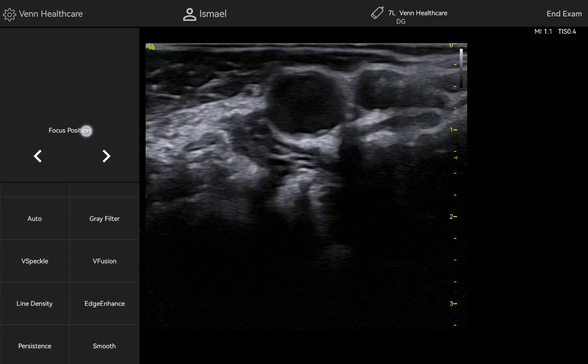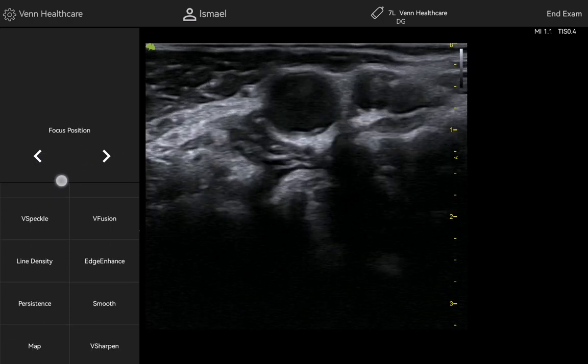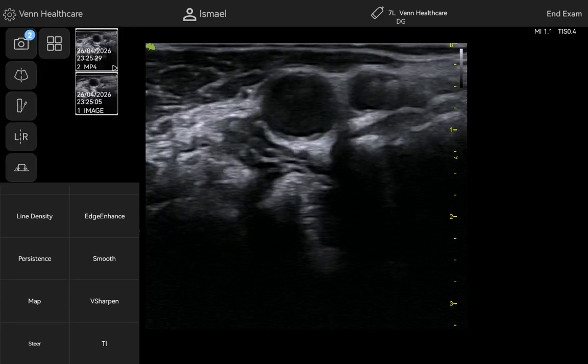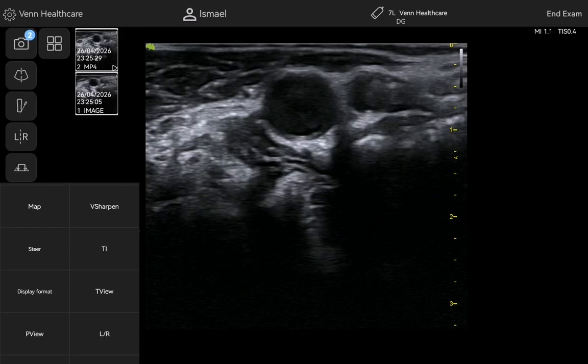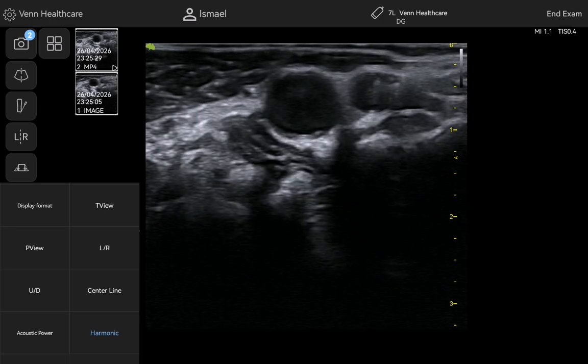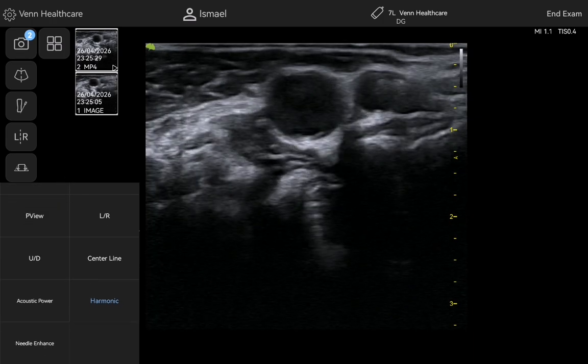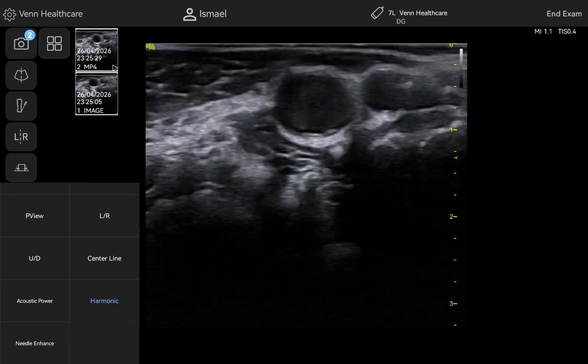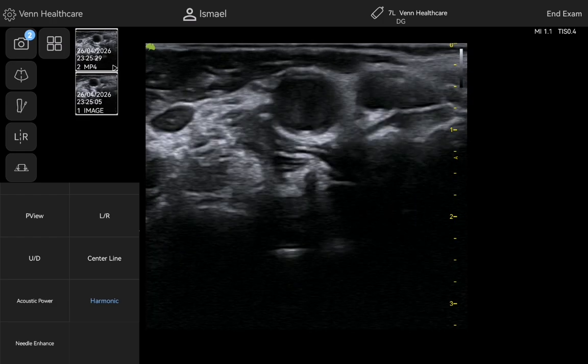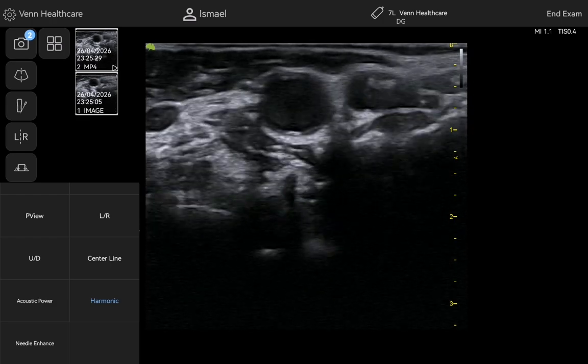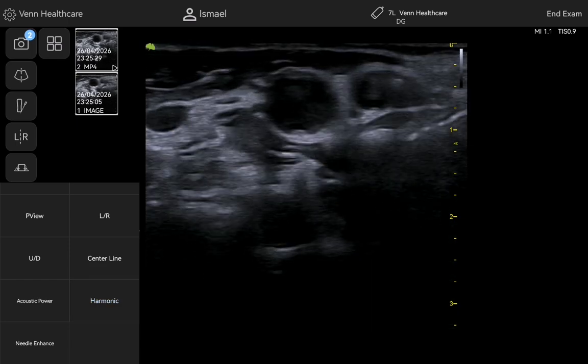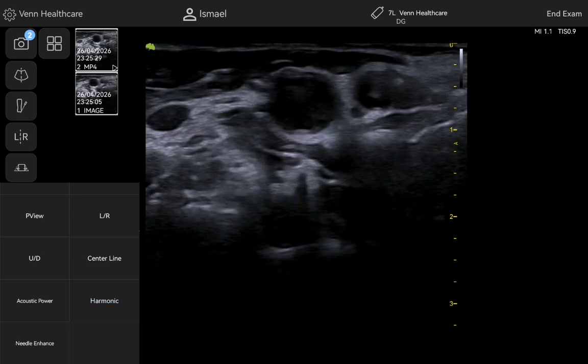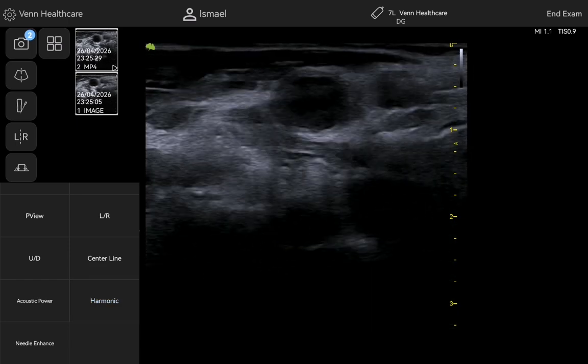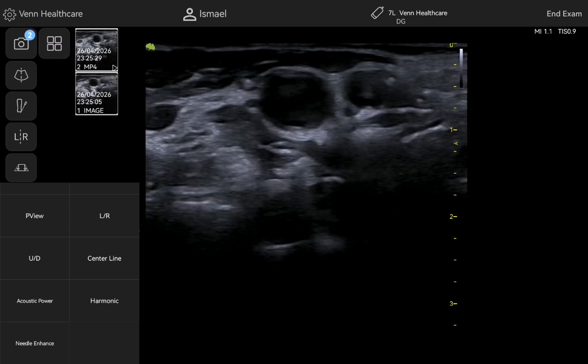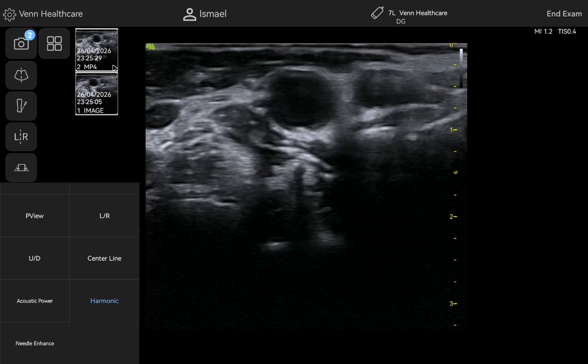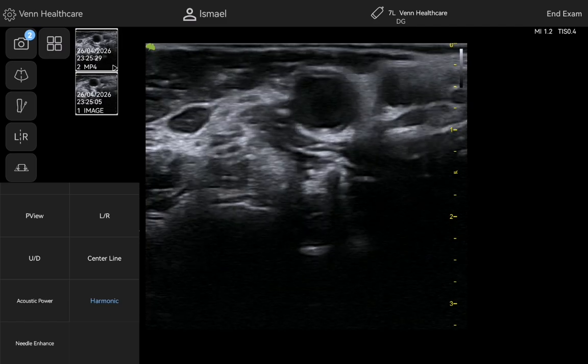You can play with the filter, the edge enhancement. You can smoothen the image. You can also change the display. You can also put the center line on from here. You can also turn off harmonic imaging. At the moment I'm using harmonic imaging. This allows you to go up to 16 megahertz. If I take it off, you see the image quality completely changes because we're using up to 12 megahertz now on normal B mode imaging. But when we go to harmonic imaging, which is default, we'll get a better image quality up to 16 megahertz.